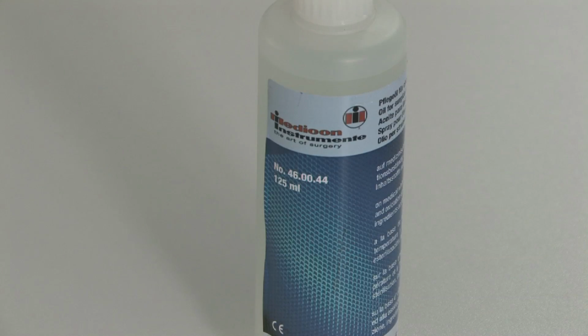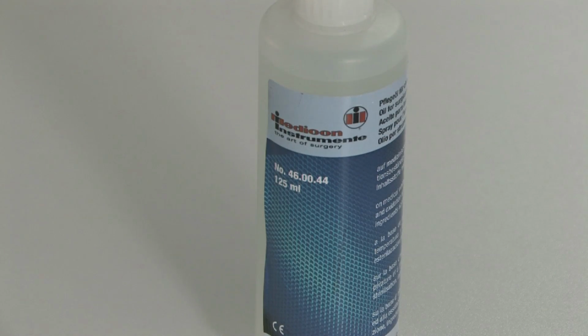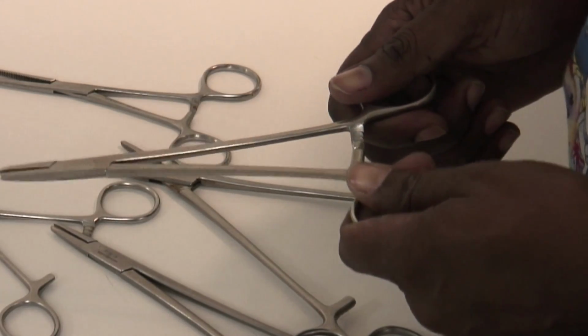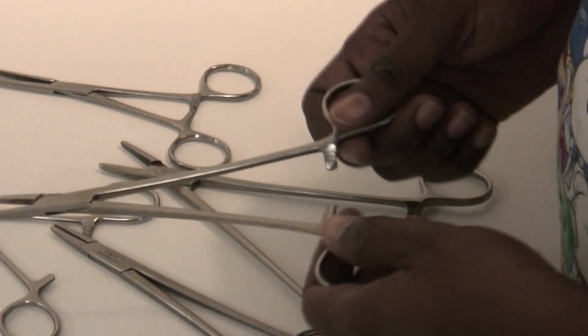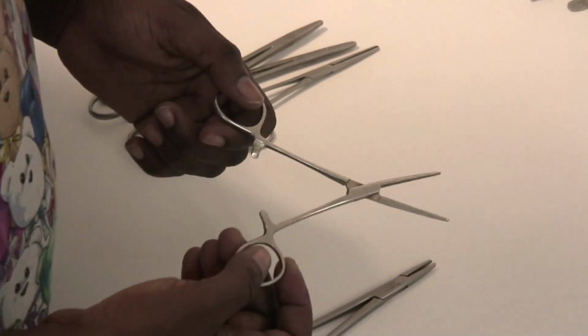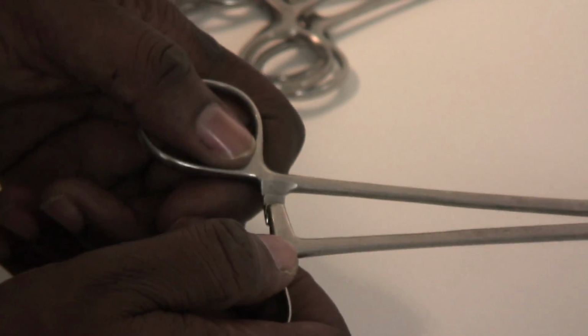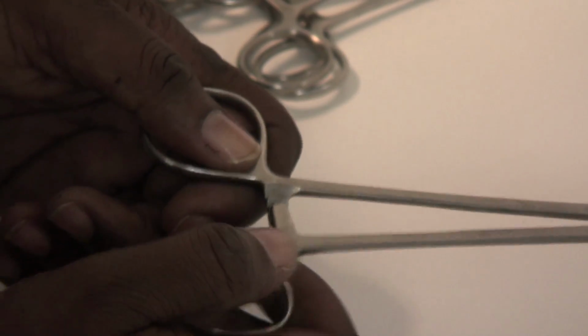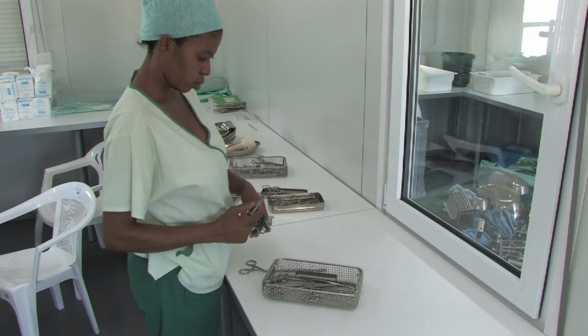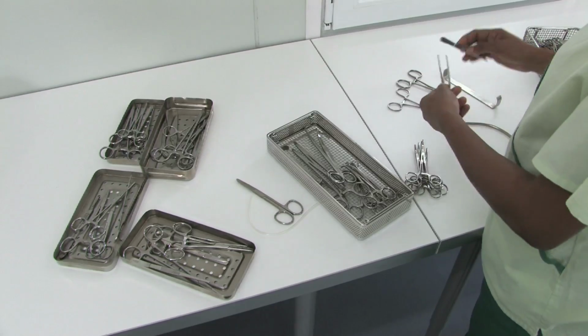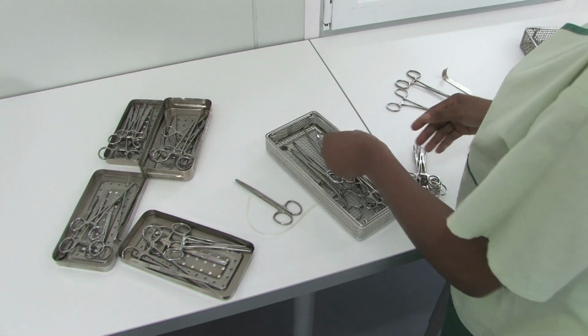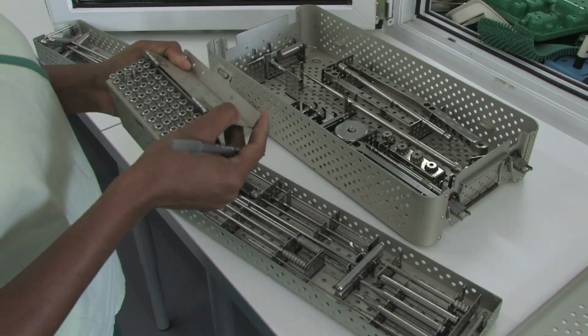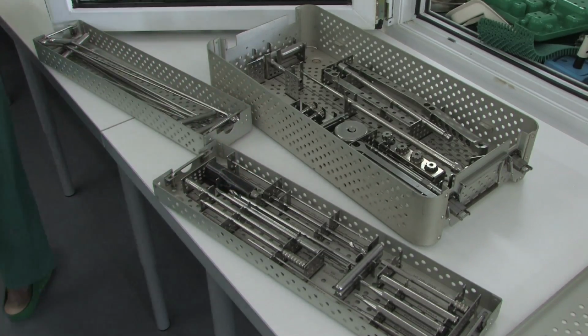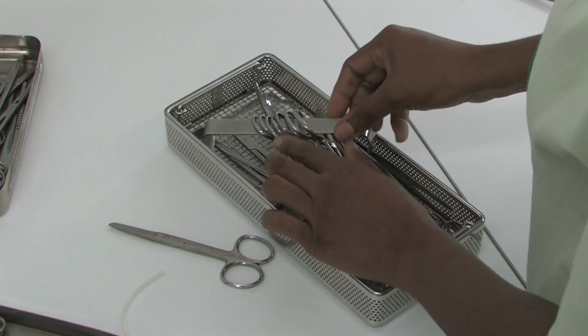A drop of silicone-free oil is sometimes needed on moving parts to make certain devices work better. It's important to lock instruments, but only at the first setting so that steam can penetrate between the different parts of the instrument. When the instruments are ready, check the composition of the sets against the pre-established lists. It's important not to mix instruments from different sets.